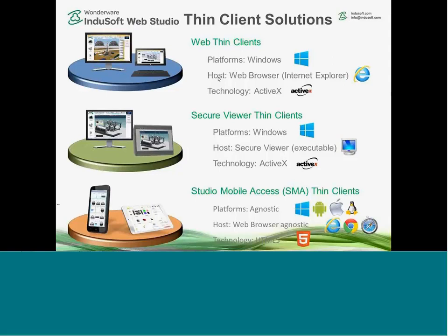They can view and, with security, optionally interact with those screens and see the real graphics and the real data. They don't need anything installed. They just point it at the IP address and away you go. So that's what's really nice about this, is because the license resides on the runtime. They don't have to license their desktop PC, and they just open up an Internet Explorer and go.